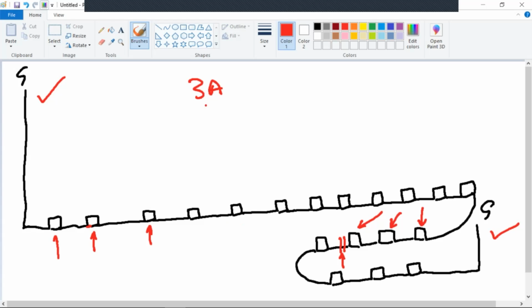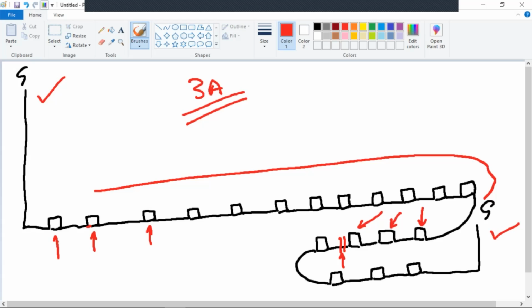But because you don't have 3 amps on the line continuously, you may have a fault anywhere. If there is not enough load, especially down here towards the end, because the load is really tapering off, you might not have enough load that if a fault occurs, if it's less than 3 amps, it won't register. So that's just a heads up on that part.